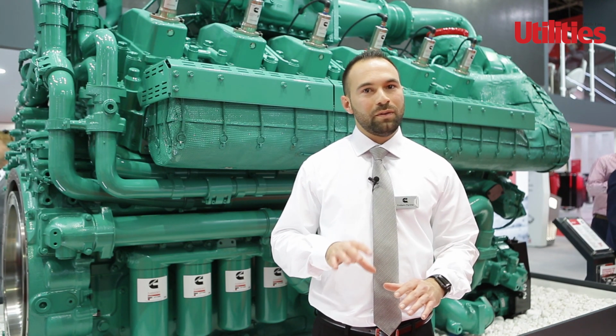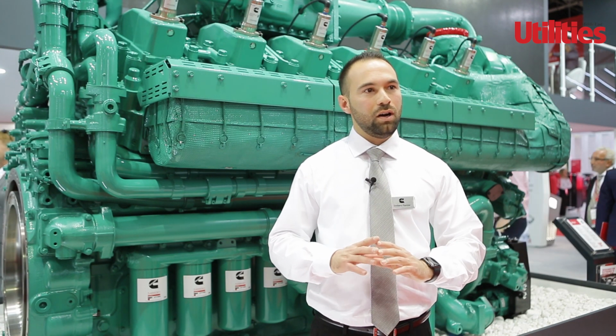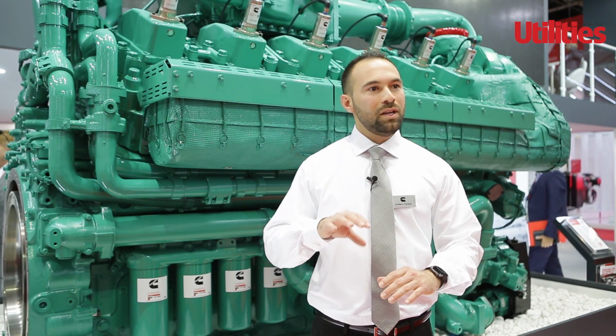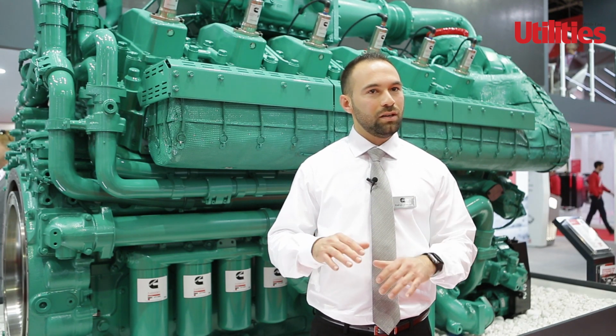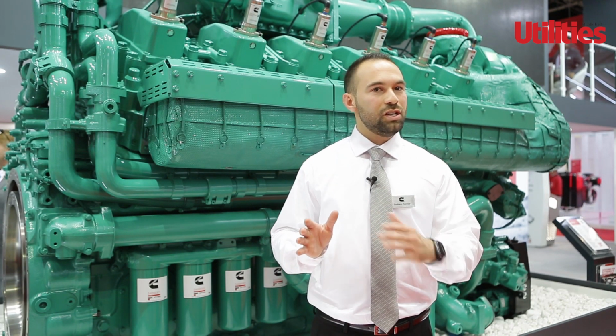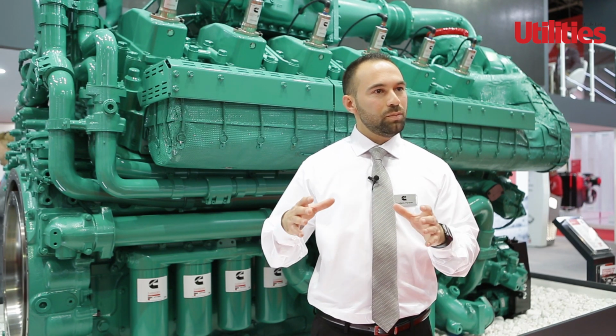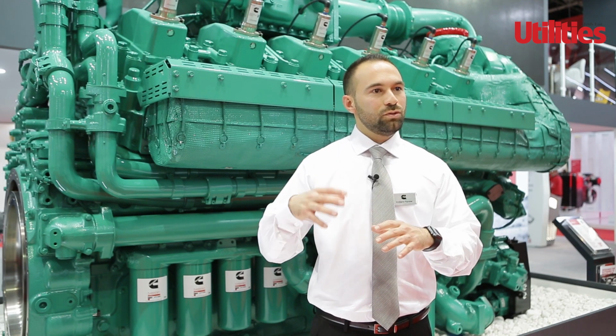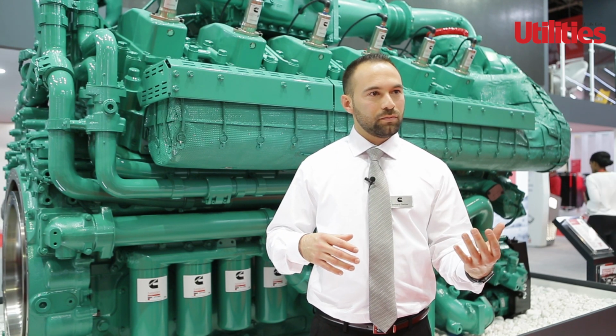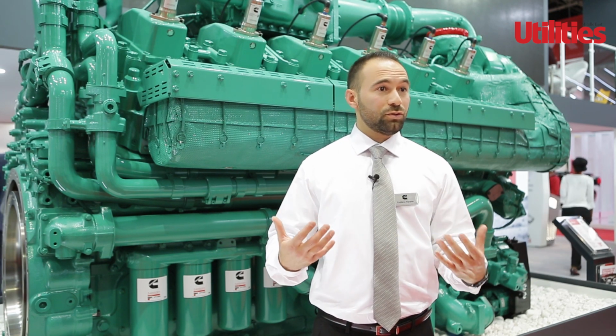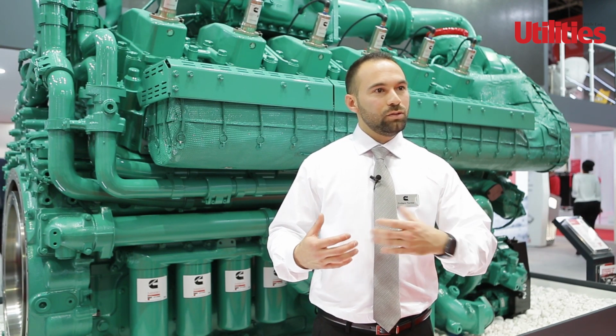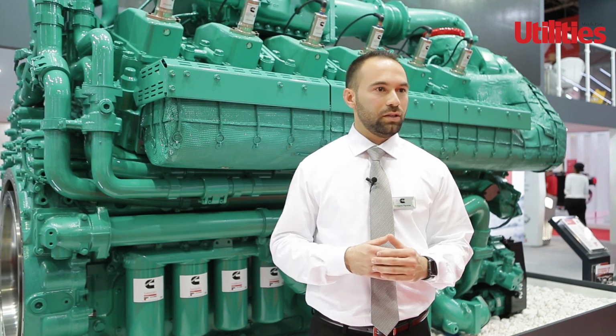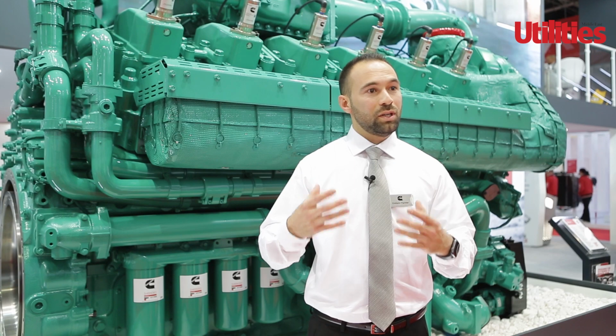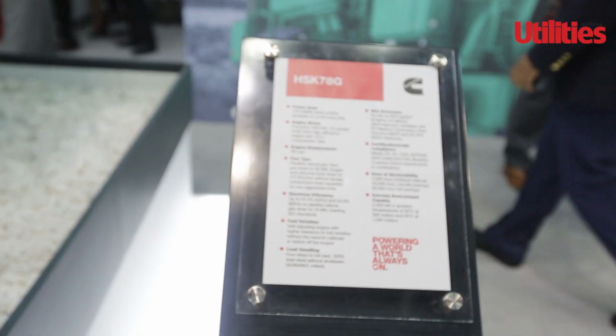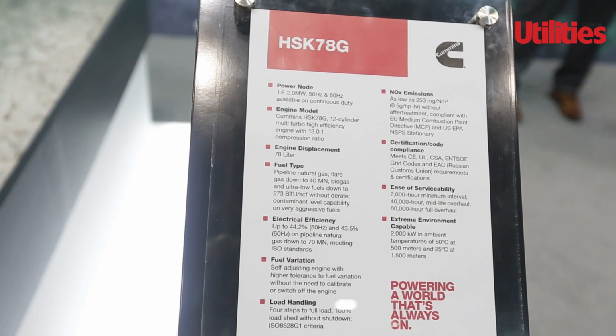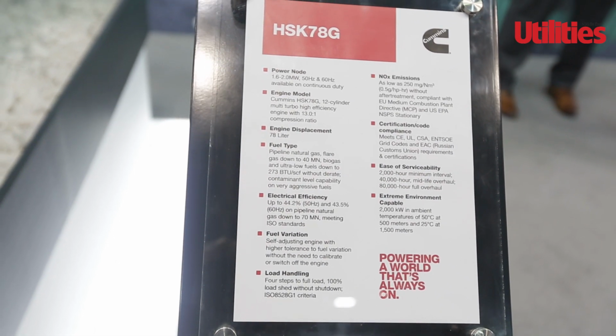The other big thing where we've done a lot of improvement, especially on service time, is that we've implemented a split core design on the coupling between the engine and the alternator. Now you can just remove the top of the coupling, so it splits, and service the coupling without having to roll back the alternator. In the event that you need to remove the alternator for some reason, we do have a rollback tool, so you can just roll it without having to lift the whole alternator. These improvements have helped us decrease the amount of service hours, going from about 20 hours down to 2 hours just by implementing the split core design.